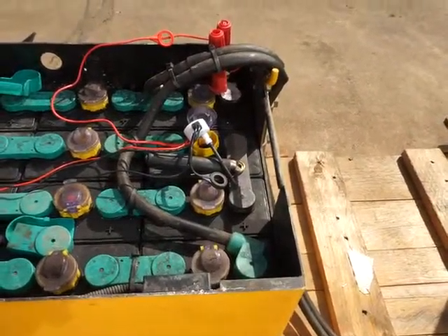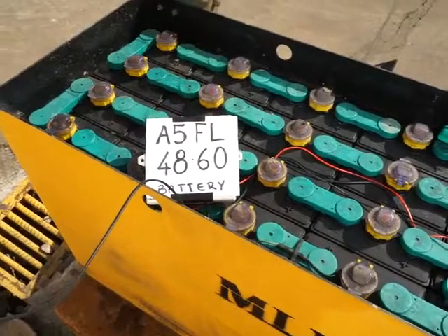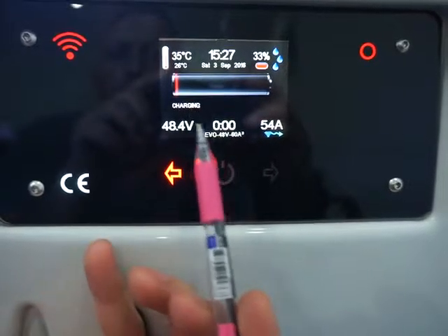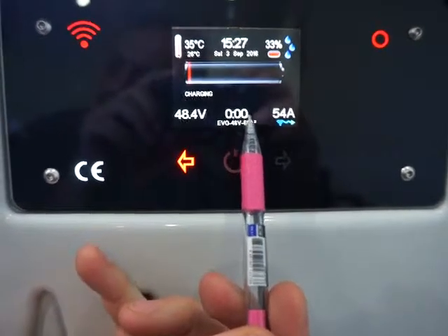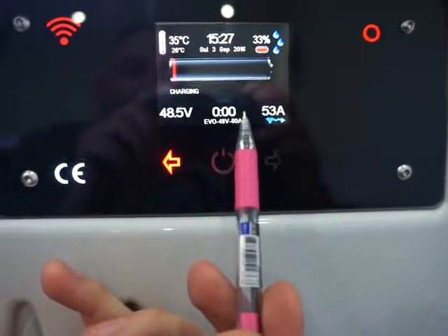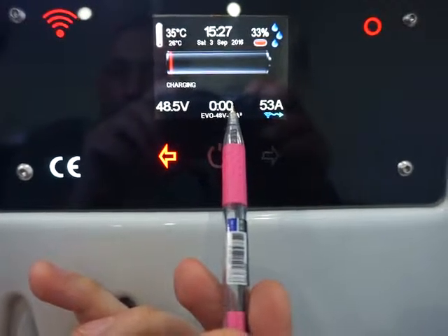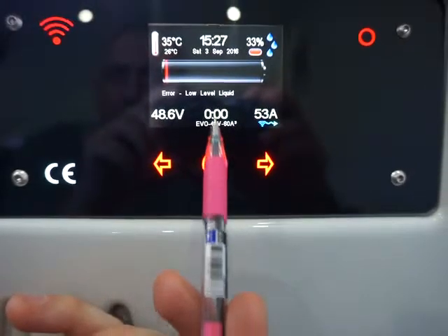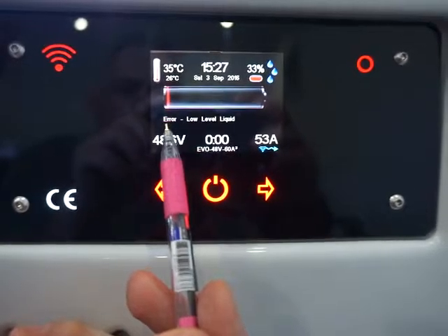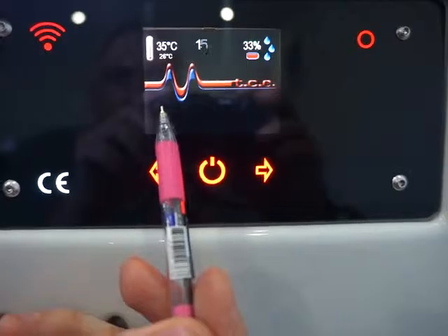You can see I removed the water level sensor and now it is blinking red. If we go back to the charger, this is now red, and the charge did not start. It will tell you there's been an error, and here you see error 4/10, low level liquid.